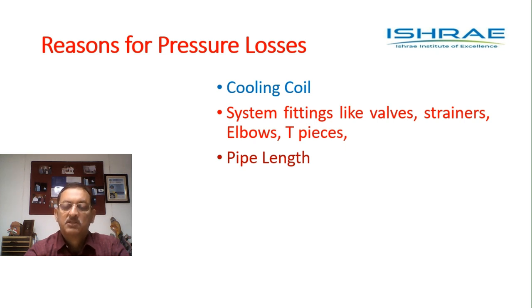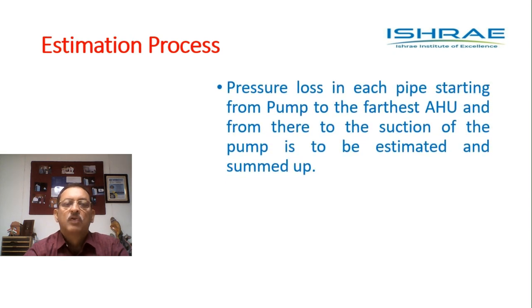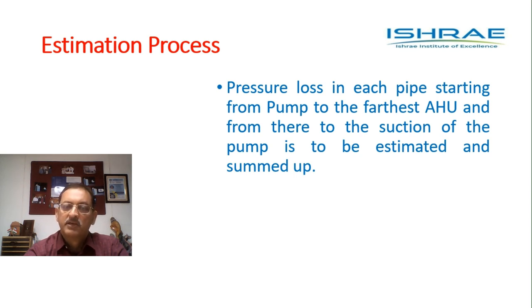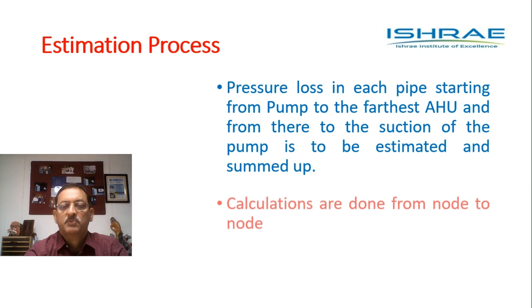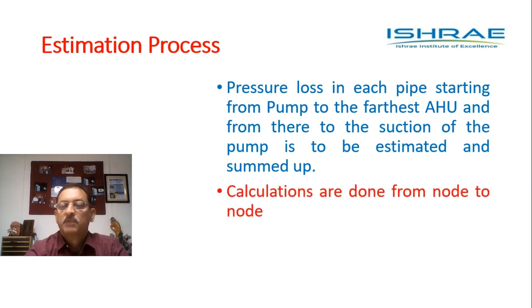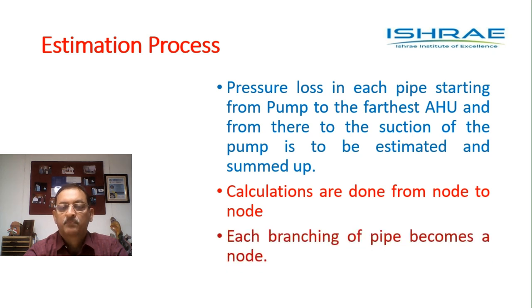The pipeline itself causes pressure loss due to frictional losses from the inner pipe material. To estimate, the entire piping system is broken into several small parts. We move from the pump to the farthest air handling unit, tracing the entire piping line there and back from the AHU to the pump suction point. The total pressure loss encountered in that path should be the minimum pump capacity needed. Calculations are done node to node — each T-piece, joint, or branching becomes a node.